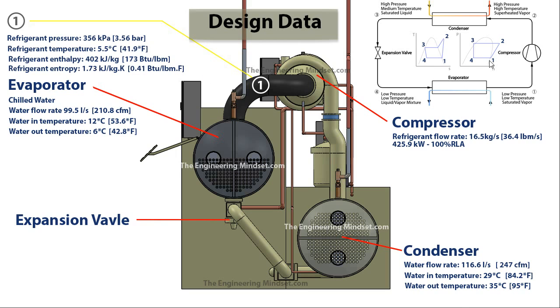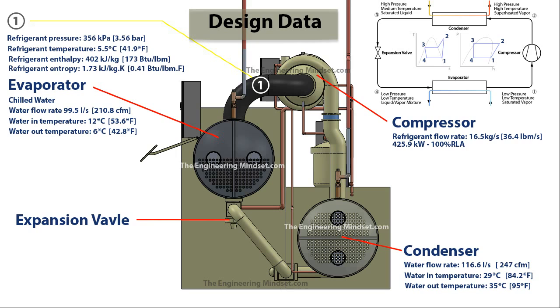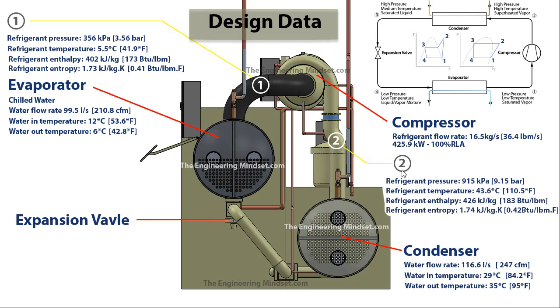We'll start at point one, marked here on the chart and on the chiller. At this point, the refrigerant pressure is 356 kilopascals (approximately 3.56 bar), the temperature is around 5.5°C (41.9°F), the refrigerant enthalpy is 402 kilojoules per kilogram (approximately 173 BTU per pound), and the entropy at that point is 1.73 kilojoules per kilogram per kelvin (approximately 0.41 BTU per pound per °F).